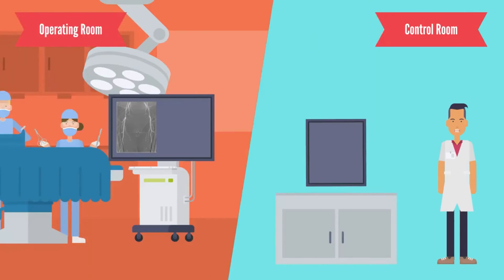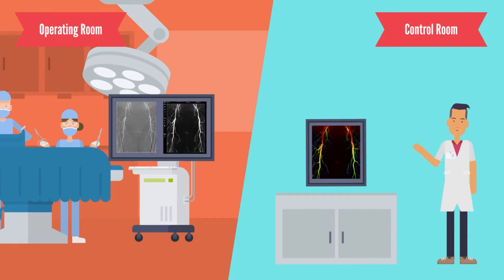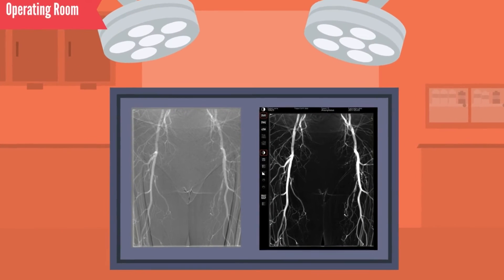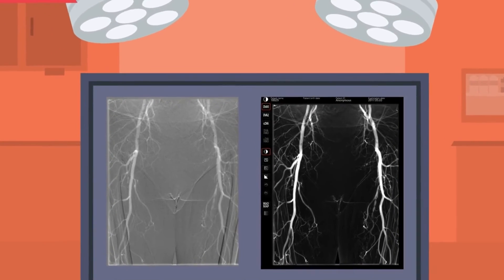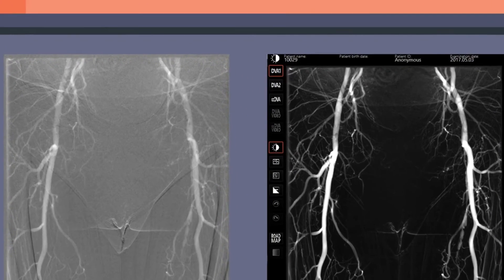The whole process takes about 1.5 seconds after the medical doctor steps off the foot switch. Practically speaking, the DVA image can be seen instantly in the operating room next to the DSA image. You also have the opportunity to modify the image in the operating room.